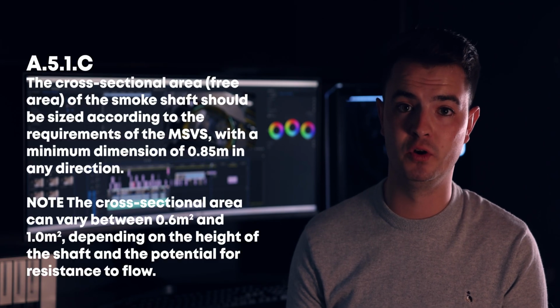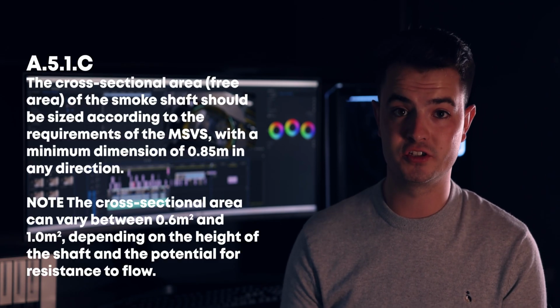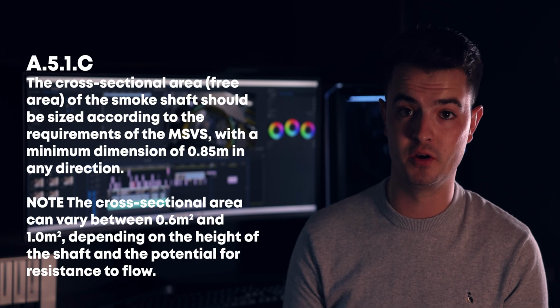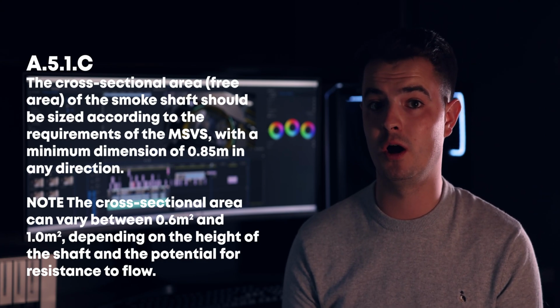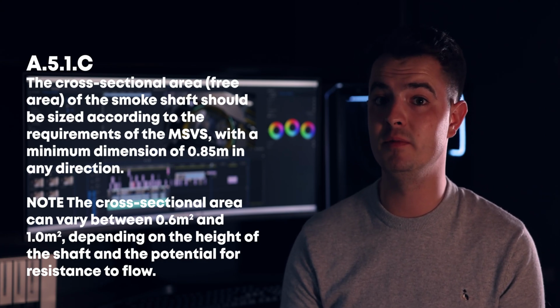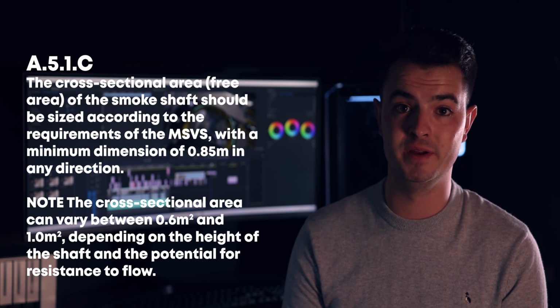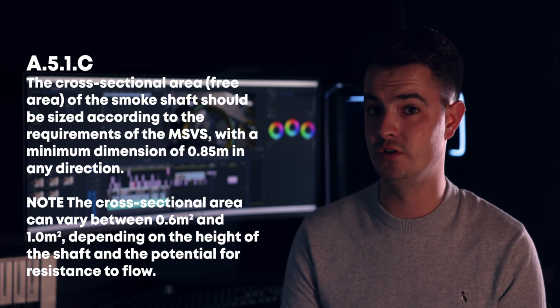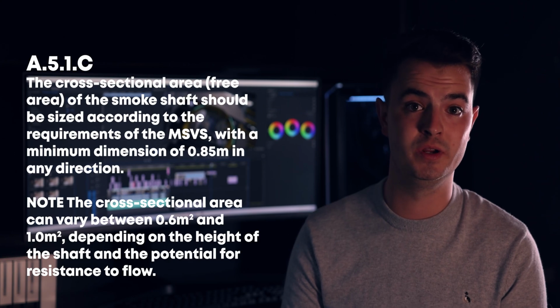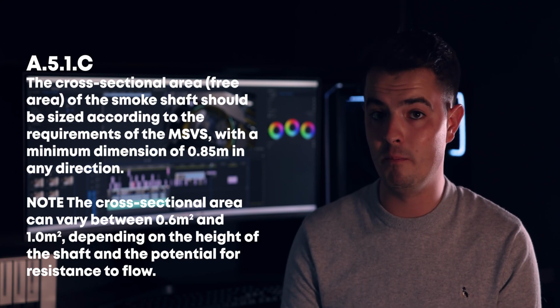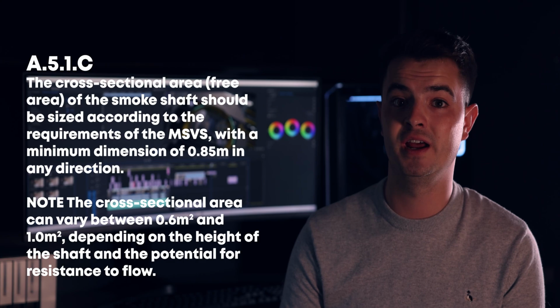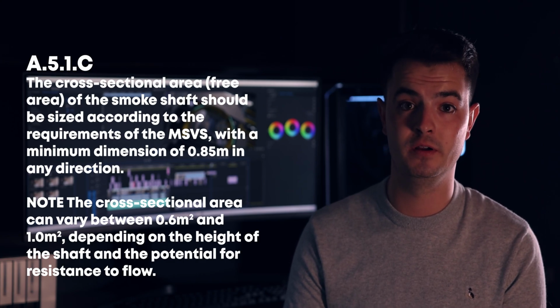An important change that is being brought in here is point A.5.1.c. The cross-sectional area, free area, of the smoke shaft should be sized according to the requirements of the MSVS with a minimum dimension of 0.85 metres in any direction. Note, the cross-sectional area can vary between 0.6 metres squared and 1 metre squared depending on the height of the shaft and the potential for resistance to flow.